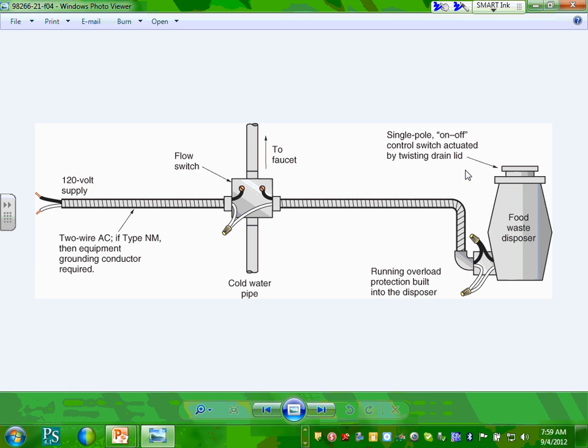Okay. Sometimes they have a system like this, guys, where you still need a disconnect for this. But what they do is they have a flow switch. Everybody knows how to use the garbage disposal. You have to put the water on, otherwise you burn the garbage disposal as it grinds, based on the manufacturer's instructions. To prevent you from activating this appliance, this is a preview for commercial, they have a flow switch here, a mechanically actuated switch. As the water goes through the pipe, it will close the contact right here.